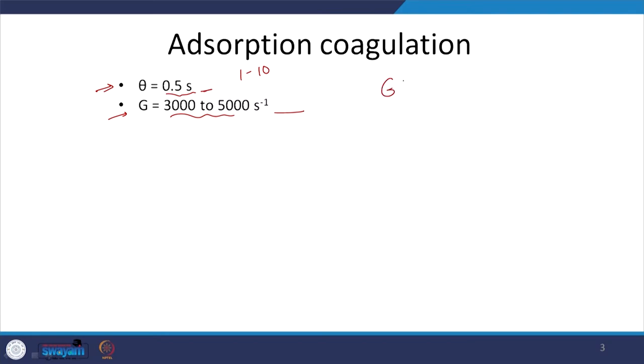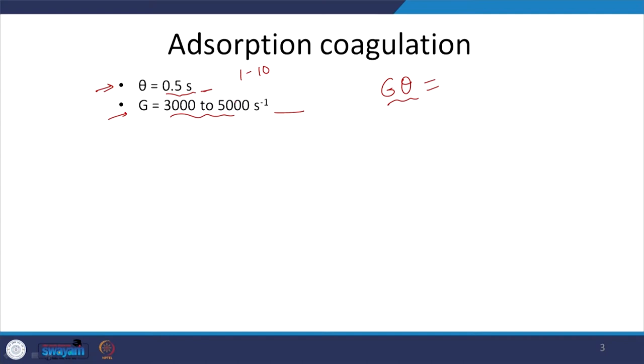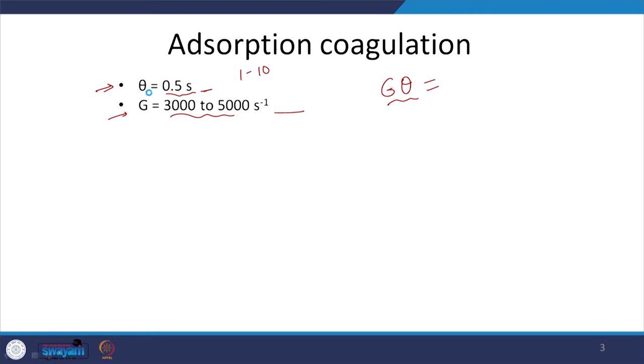In general we are concerned with G·theta, but it is not that this is a single equivalent value. Even though G·theta for adsorption coagulation might be comparable to sweep floc coagulation, we also need to be concerned about G and theta as independent variables, because they will affect the kind of mechanism and how effectively it proceeds. That is something to keep in mind.